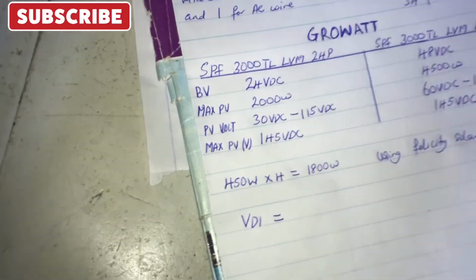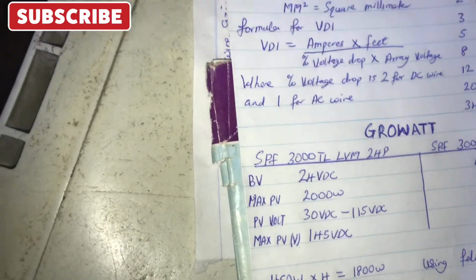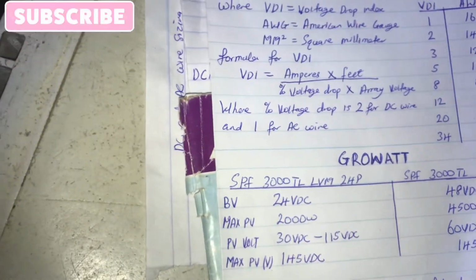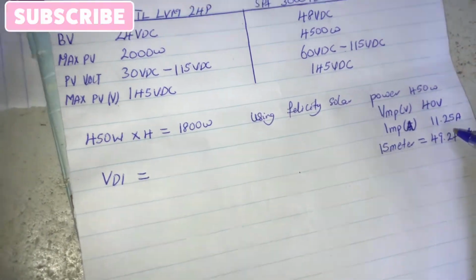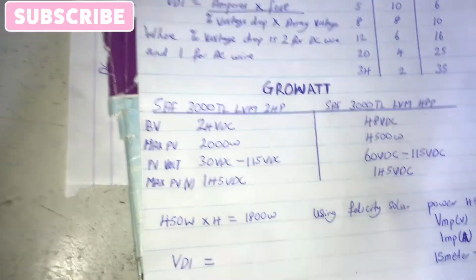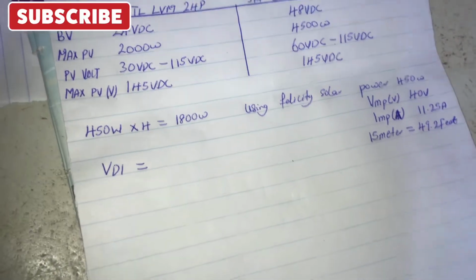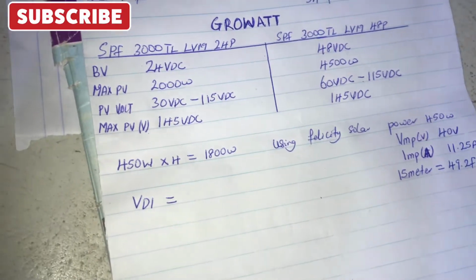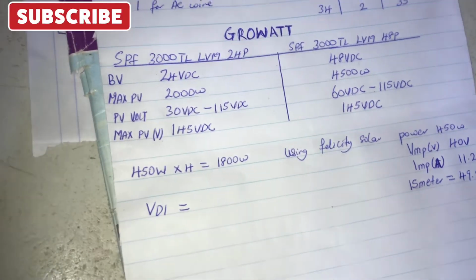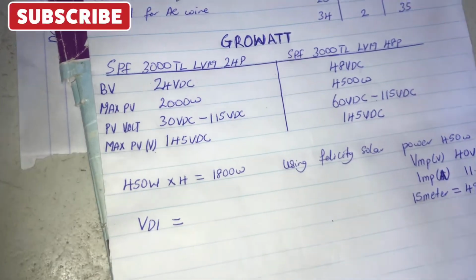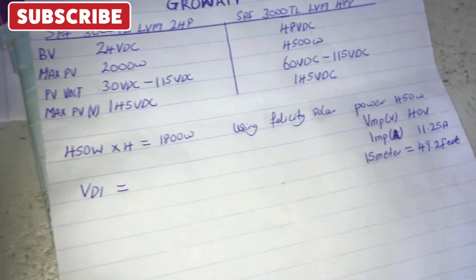So with this, what we have here now is VDI, which is amperage, which should be 11.25 multiplied by 2, because what we are doing is 2 series and the 2 circuits in parallel, giving us a double amperage.